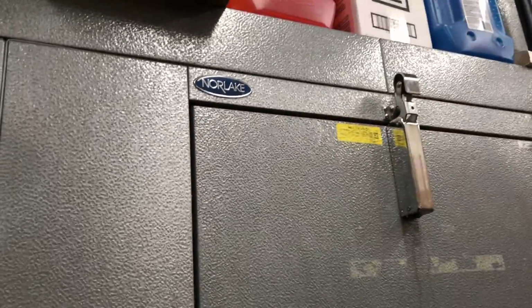It's a walk-in, but it's remoted. The condenser units are on the roof. Came in, listen. What do you hear? It's either low on charge or high head, so let's get on top here. I'm gonna check out the little line sets and it might tell us a story. Get on top of here, pretty simple. See what the problem is.